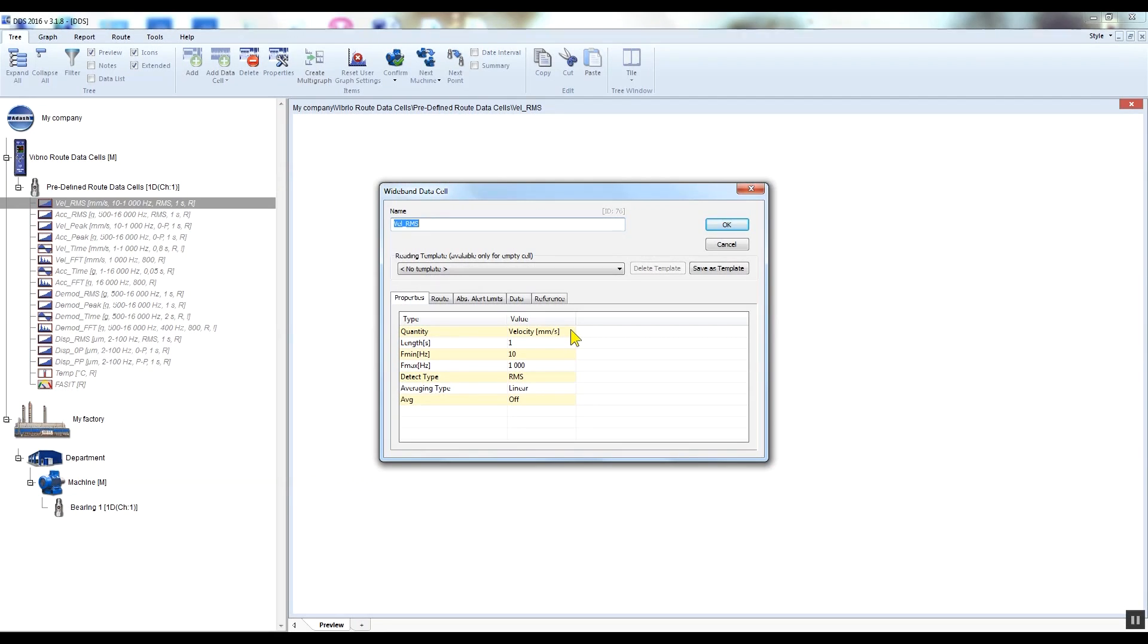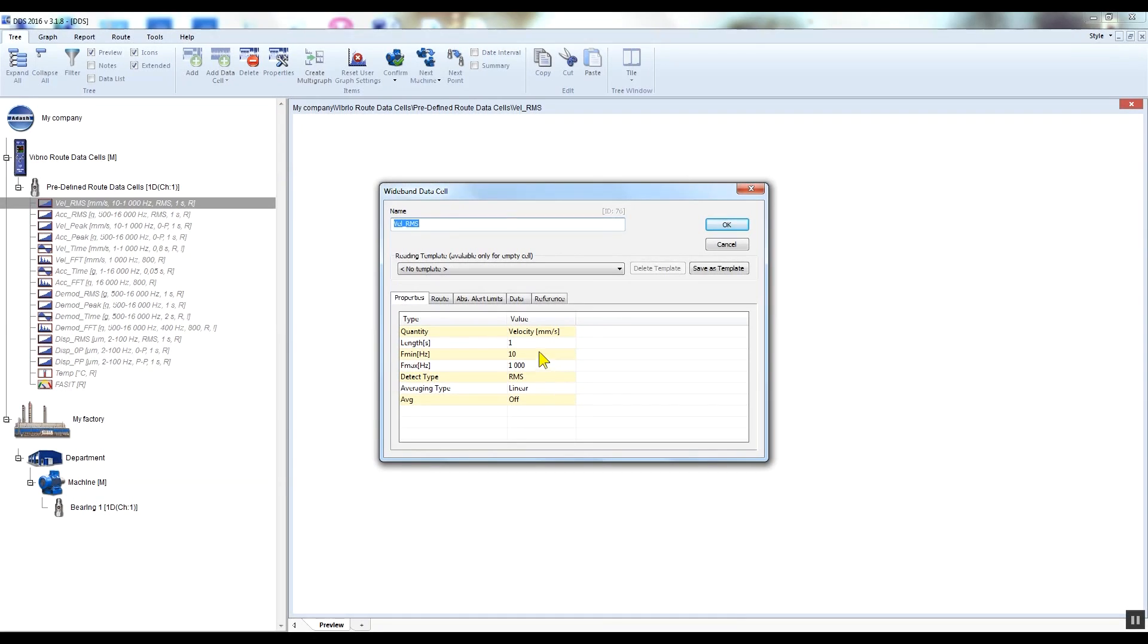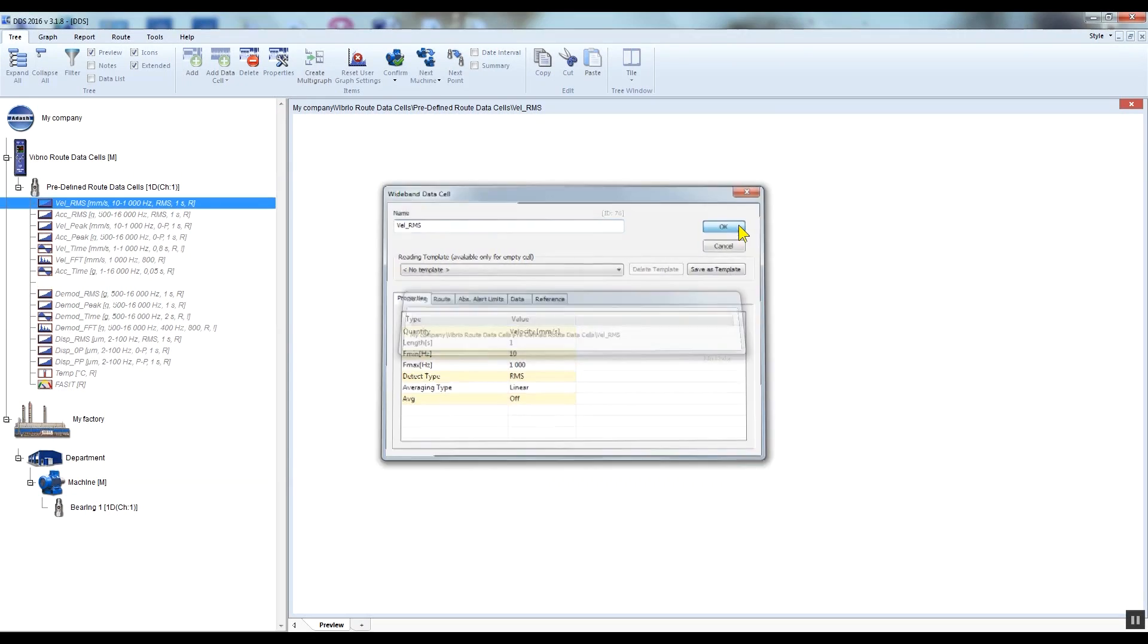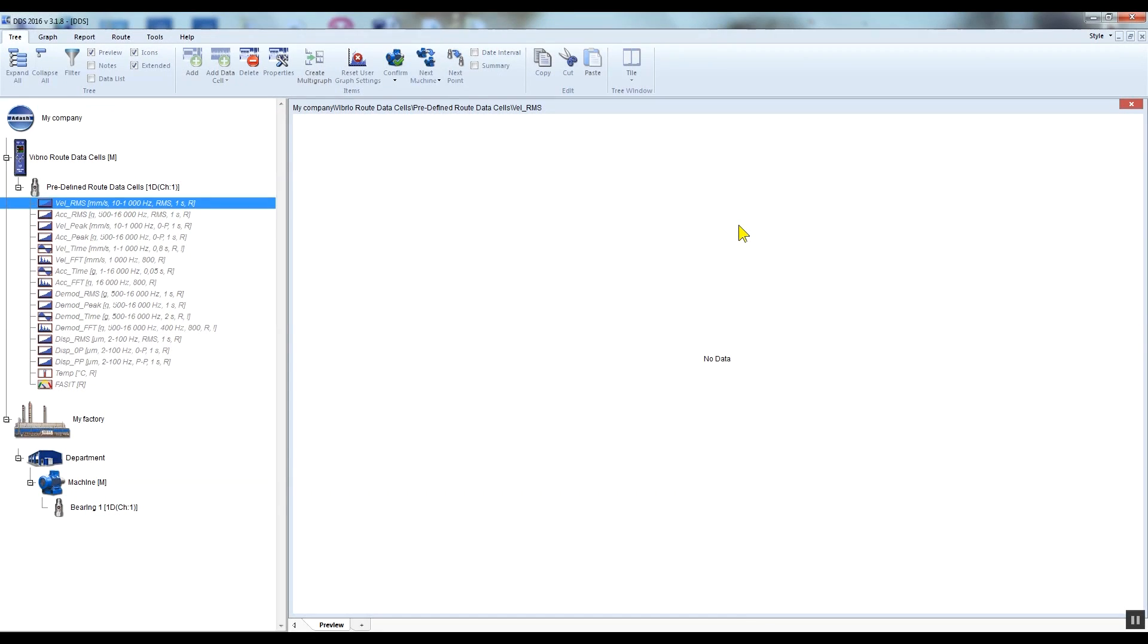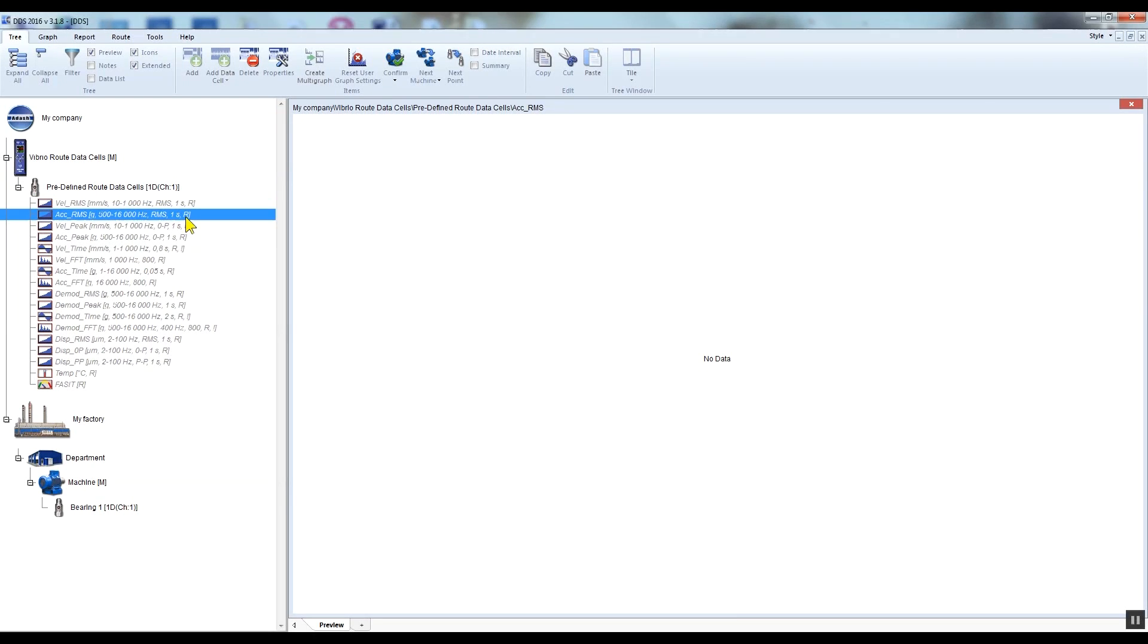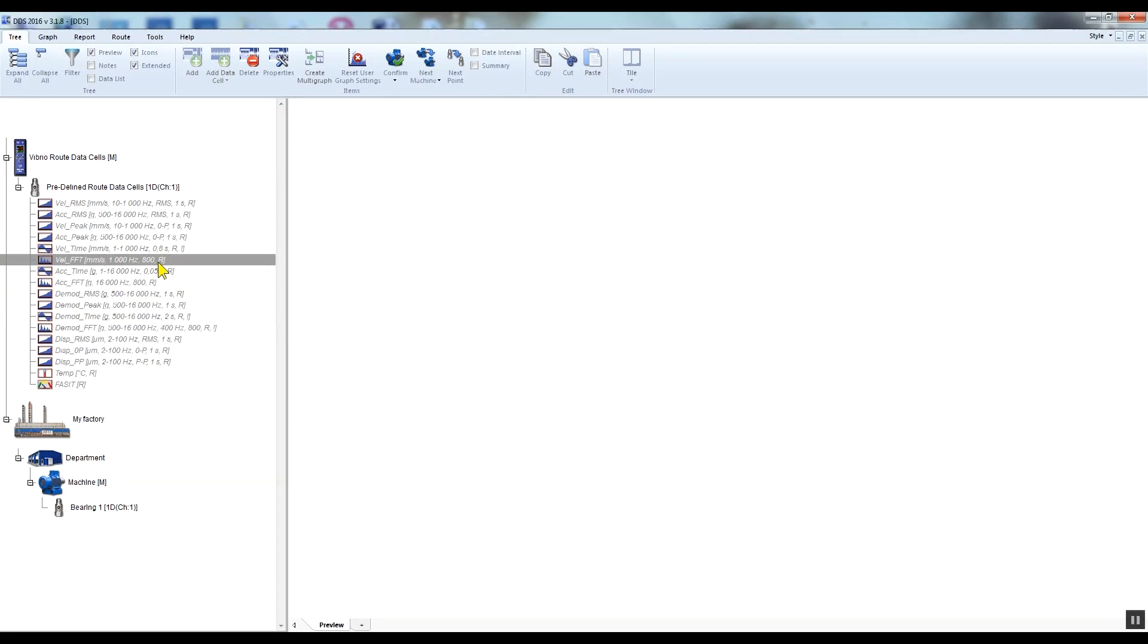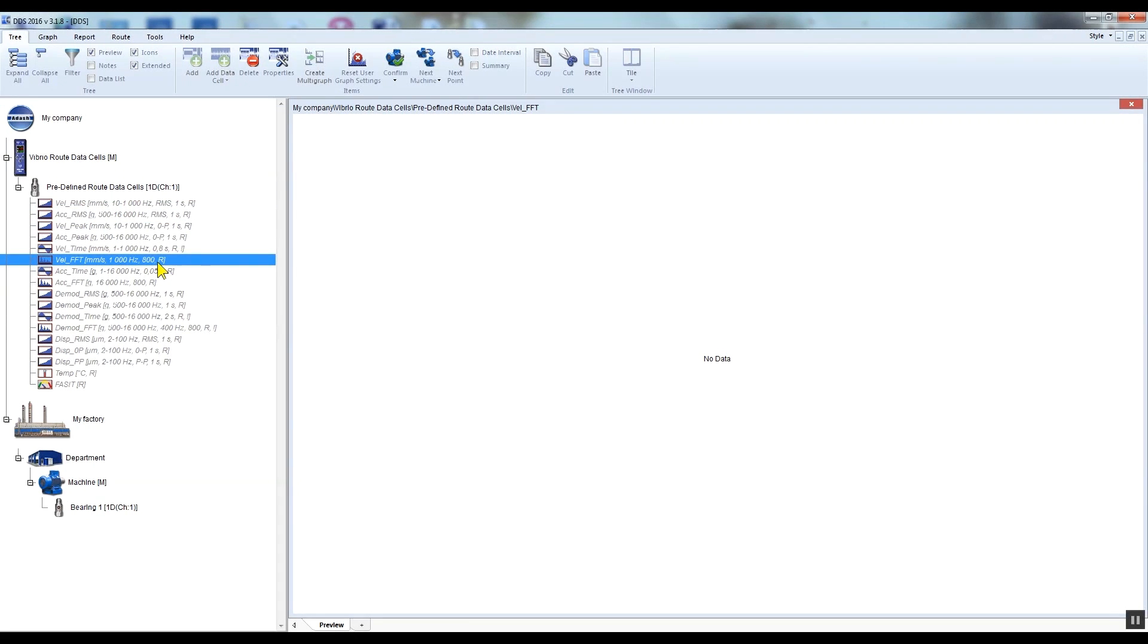This means that with the vel RMS data cell we will be measuring the overall value in velocity millimeters per second RMS in the 10 to 1000 Hertz frequency range. You can click on any data cells properties to see its settings. Let's say that we want to measure velocity RMS, acceleration RMS, and velocity FFT under our Bearing One measurement point.